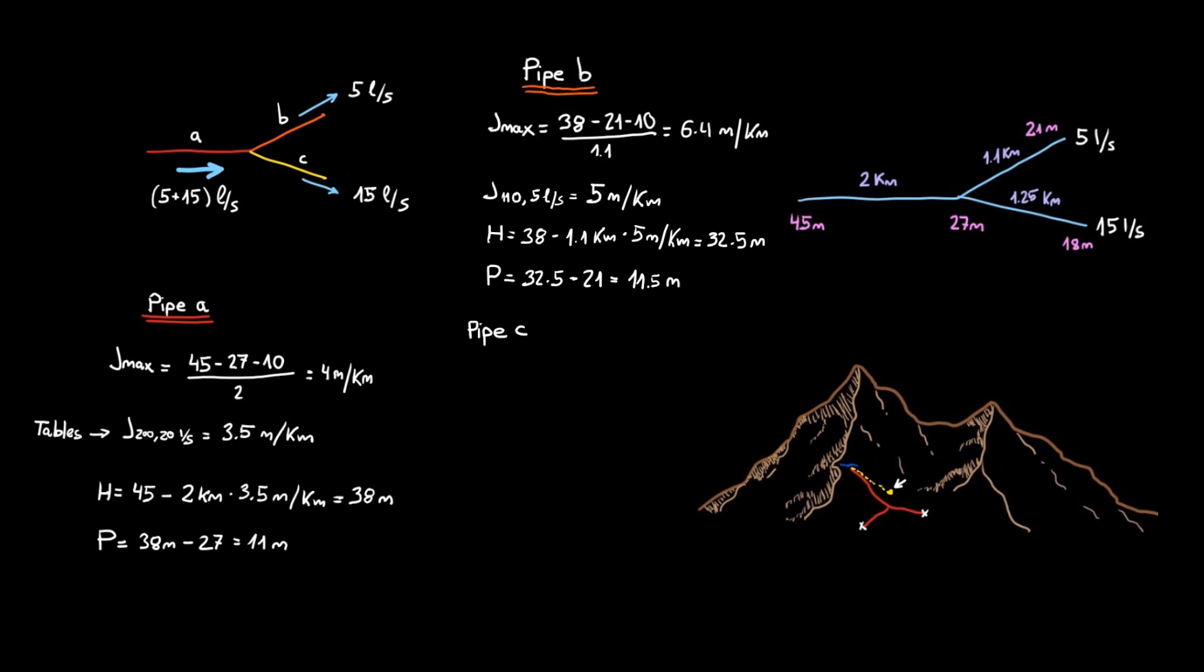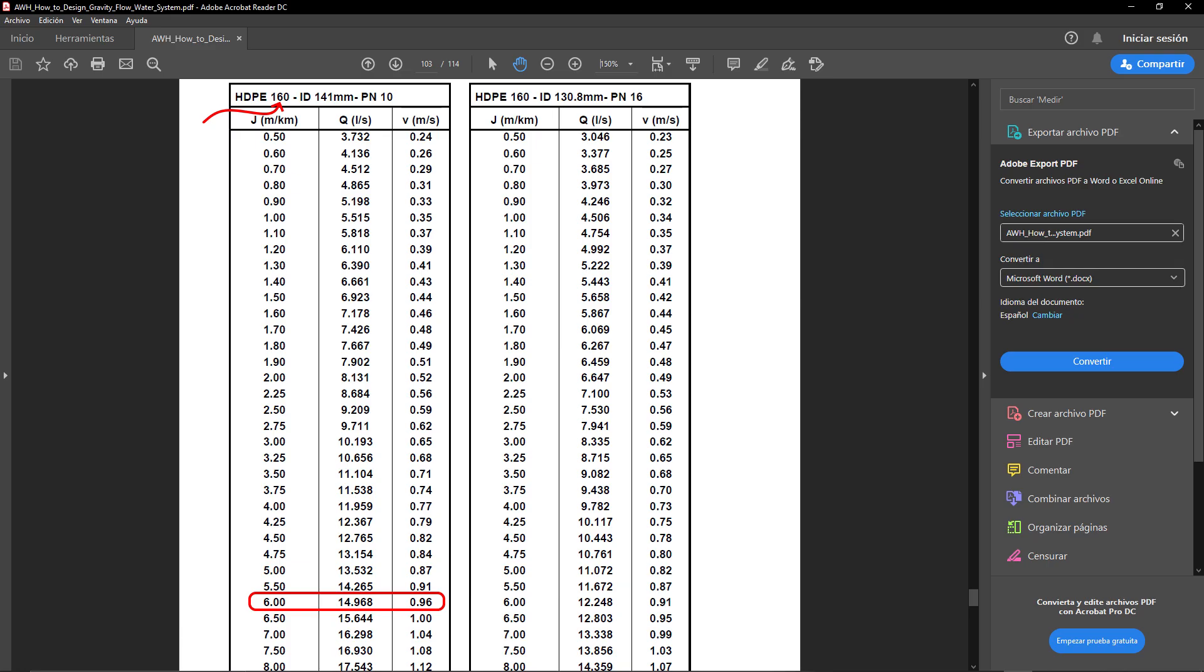Pipe C repeats the process. We need to find head loss values below 8 meters per kilometer for 15 liters per second. The closest value is for 160 millimeter pipe. We then find head and pressure values.